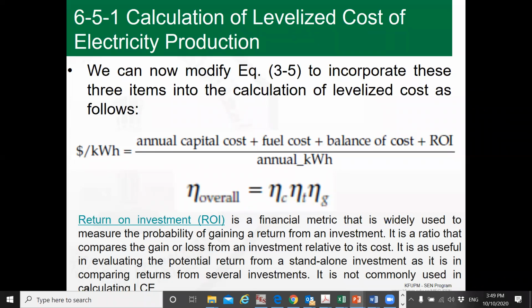Also, your electric generator: you have mechanical energy coming to the electric generator, and out comes electric energy. But inside the electric generator there is friction in the bearing. There are also electromagnetic losses in the coil of the generator, so it doesn't have 100% efficiency. So when you talk about the plant, you have electricity at the transformer or at the bus bar of the power plant, and you have fuel at the input. The ratio of the energy of this electricity to the chemical energy in the fuel should include the combustion efficiency, the thermodynamic cycle efficiency, and the electric generator efficiency. You multiply the three, and this gives the ratio between the net electric power at the bus bar of the plant and the chemical power or energy in the fuel.